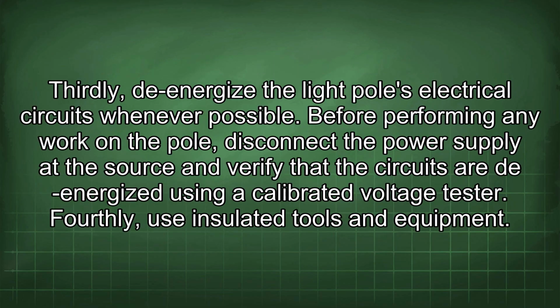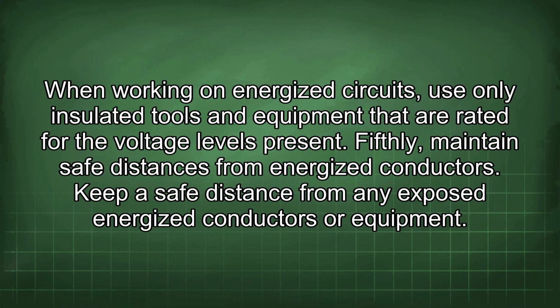Thirdly, de-energize the light pole's electrical circuits whenever possible. Before performing any work on the pole, disconnect the power supply at the source and verify that the circuits are de-energized using a calibrated voltage tester. Fourthly, use insulated tools and equipment. When working on energized circuits, use only insulated tools and equipment that are rated for the voltage levels present.